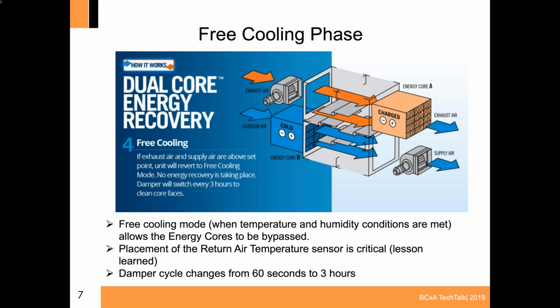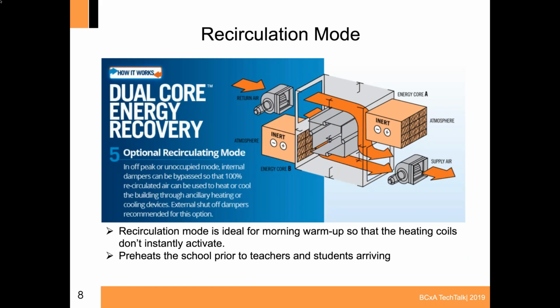So this is the free cooling mode. And then you have a full recirculation mode. This is ideal for a morning warm-up so that your heating coils don't get blasted with cold outdoor air right away. You would have these dampers in this position where all of the return air is directed into the school, and it preheats prior to any teachers, students or building occupants arriving.